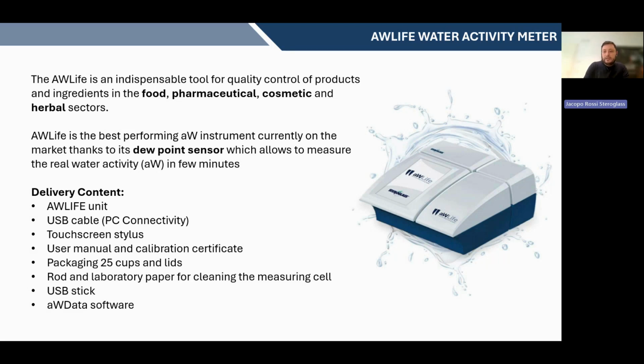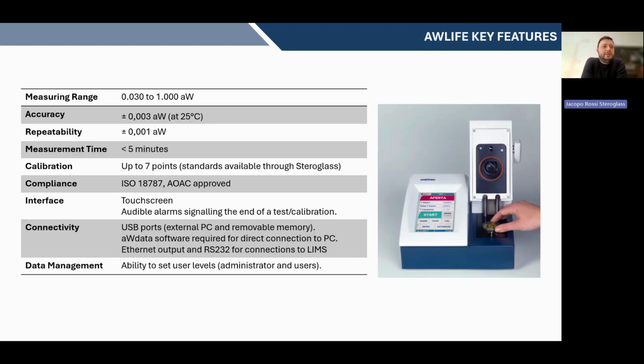It's a very compact benchtop piece of equipment. And these are the features. You have a complete measuring range for the whole range of water activity values. The accuracy and the repeatability are the ones required by ISO 18787. Thanks to the dew point sensor, you have the possibility to run an analysis in less than 5 minutes. And you also have the possibility of a complete calibration and a complete control range.